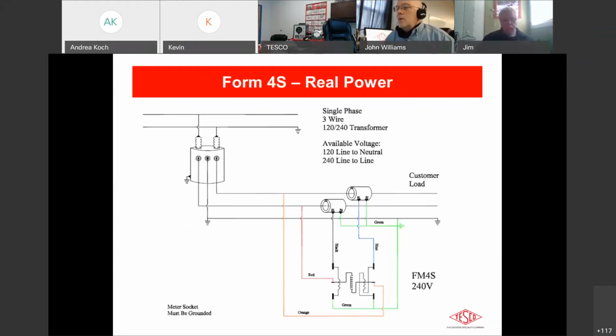The next one we have up is a step up in complexity again. We have now our 4S transformer rated meter, similar type application, 3-wire service. We take the 240 volts across the potential coil, but this time instead of doing that double wrap and the 0.5 factor on the meter that we see on the 3S, the 4S has those two current coils and can accept the outputs from the two CTs. And I think this is the one you wanted to talk about, Kevin, right?